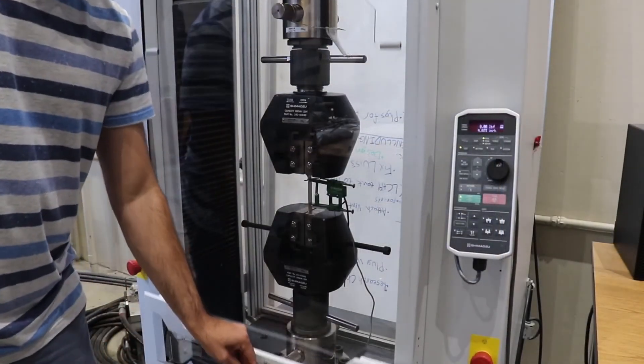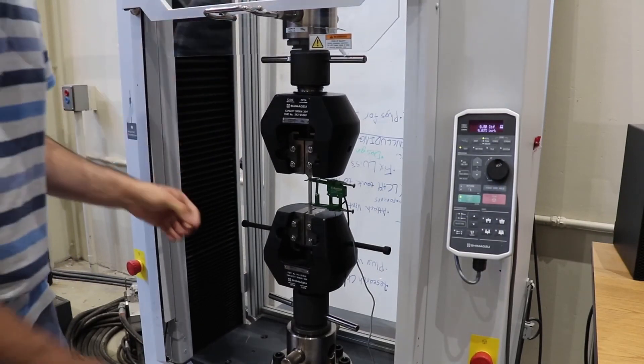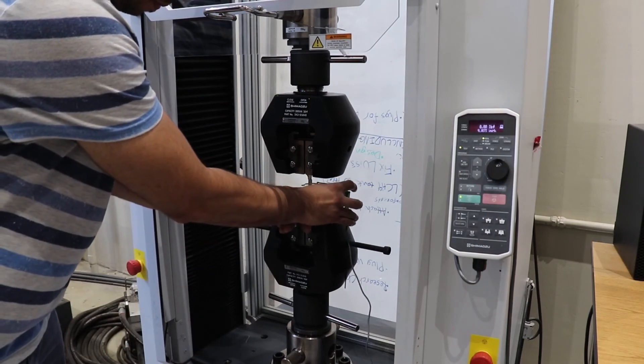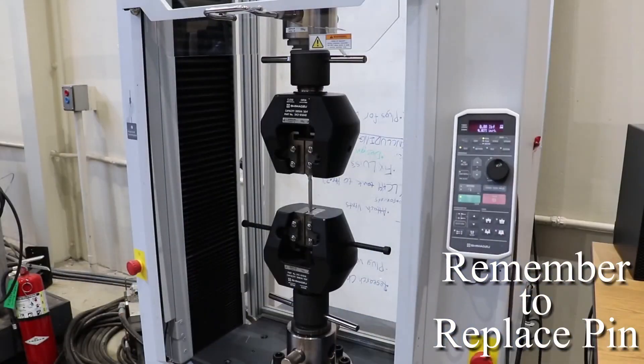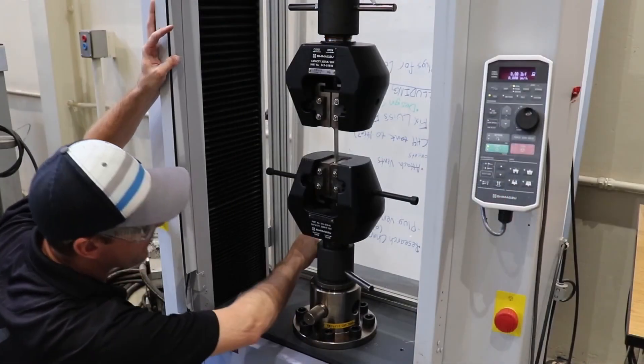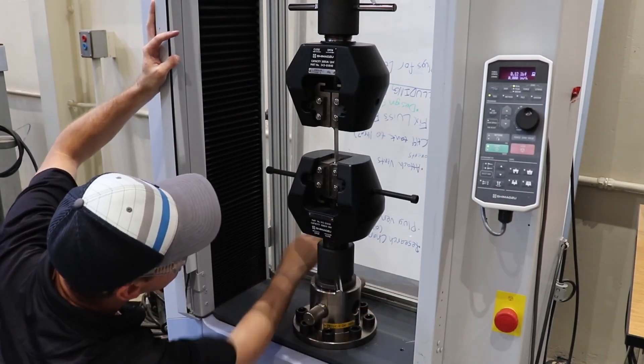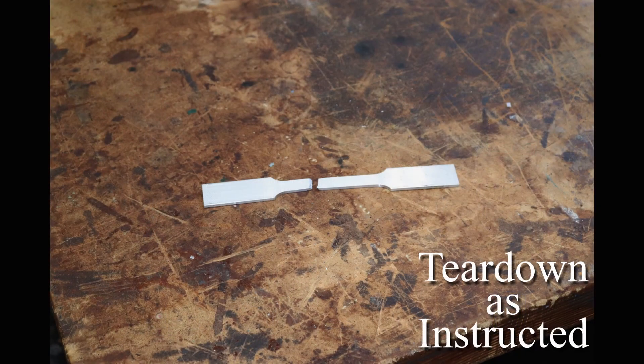We now begin the teardown process. First, we raise the shield. Next, we remove the extensometer being very careful as it does not have its pin in at the moment. Our next step involves untightening the jaws and removing our used specimen. Thank you for watching the tension tests using the Shimadzu. Tear down as your instructor requires.